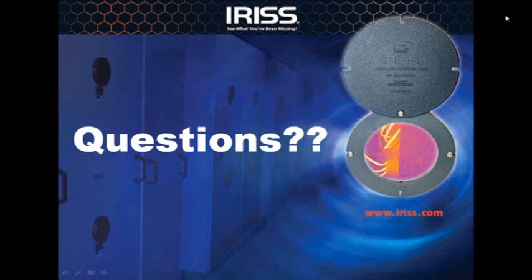That's the official line. I always speak to customers, and the way I say it is that there are many modifications that we make on our switchgear on a daily basis that really change its original design verification. So for instance, we might change the breaker, we might put new line feeds in, we may put a different type of control system in there, we may put different ammeters in there. We would do a gazillion modifications and we wouldn't reclassify because it's something we've been doing for a long, long time. Infrared windows or ultrasound ports are considered alien to what we do.